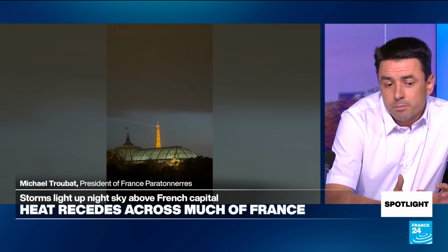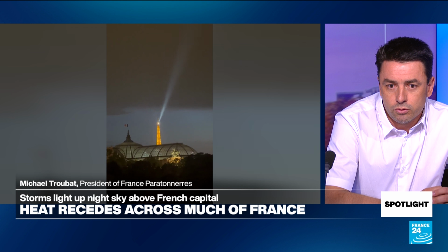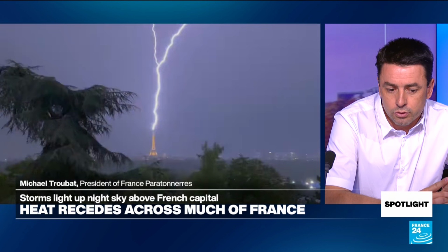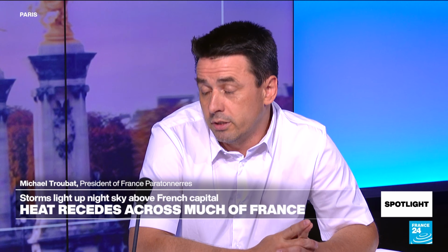And we can see how to improve things. When we are doing the maintenance and inspection on site, we know how to improve components in comparison to what had been done at the construction of the tower. It's interesting to be able to have a lot of data each year and to improve the conductors, the section of the copper, the grounding, many things.